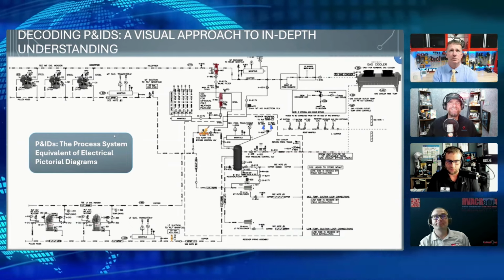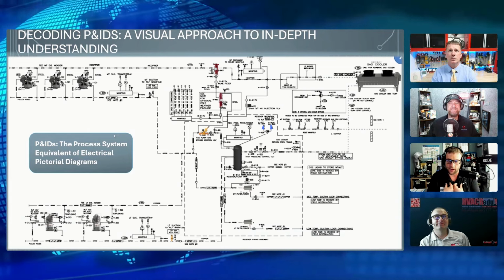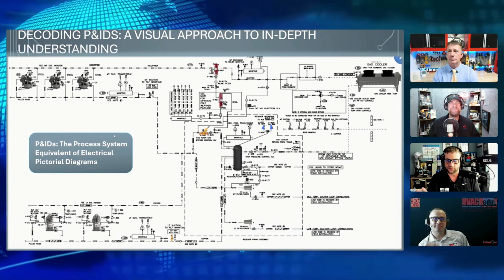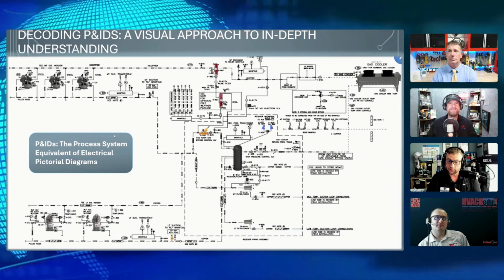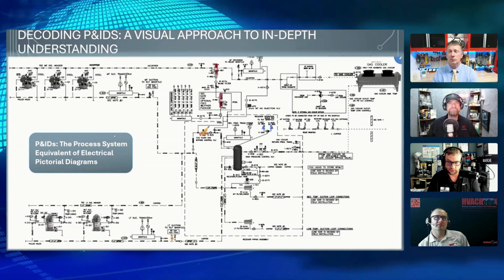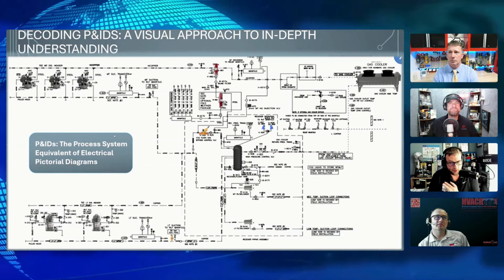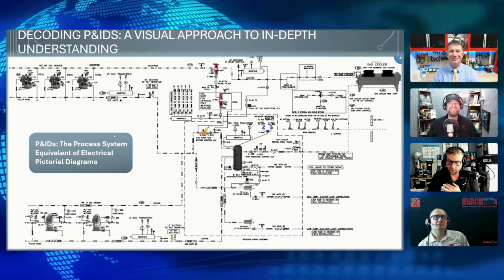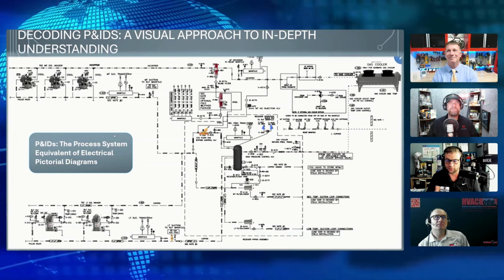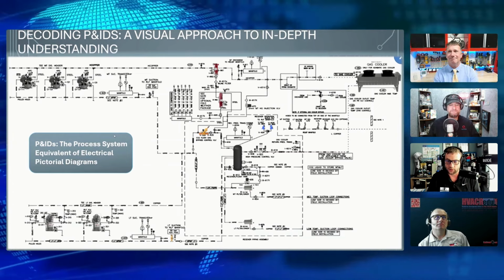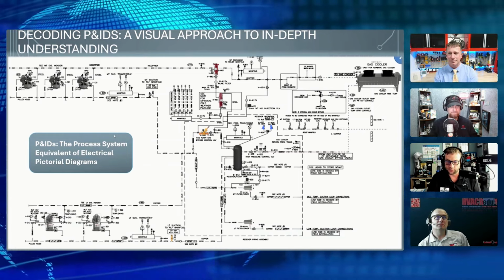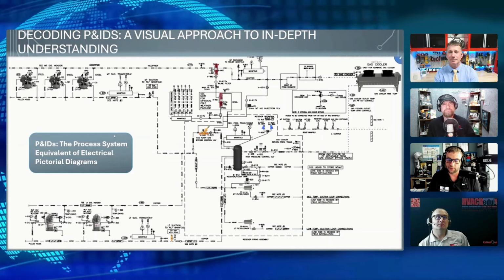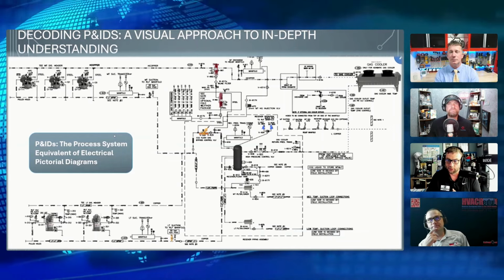Chart. Yeah, 100%. When I go to diagnose something, if I've never seen the system before, give me a P&ID, give me an SOO, sequence of operation. And if you've got a program, I'll take it as well. And the rack piping for the store. I'll read that on the airplane if I'm getting flown out somewhere, and basically run through the thing. So by the time I get off the airplane, I don't look like an idiot, like, I don't know where that is.